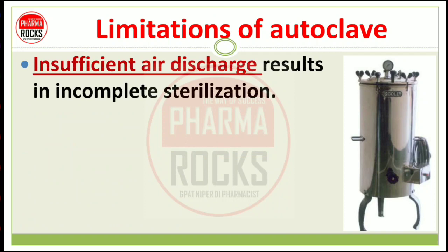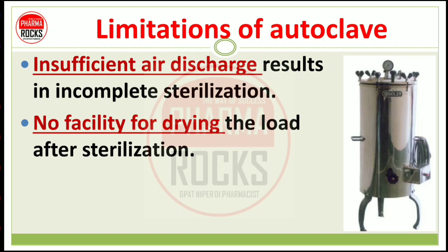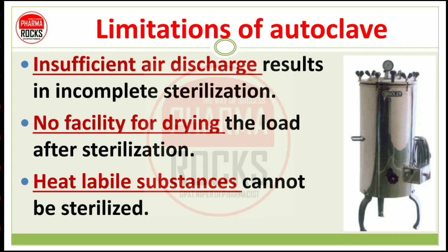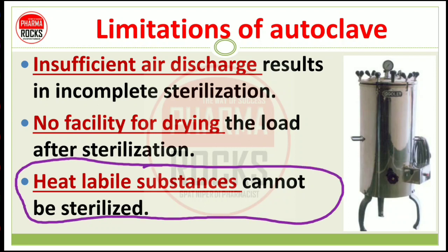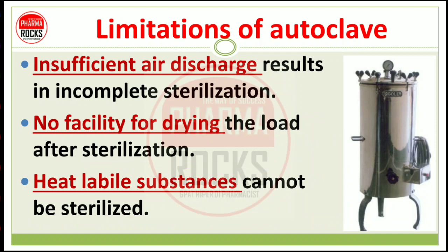What are the limitations of autoclave? Insufficient air discharge results in incomplete sterilization. No facility for drying the load after sterilization — drying ka koi mechanism nahi hai. Heat-labile substances cannot be sterilized — jo thermolabile, heat sensitive material hai usko is technique se sterile nahi kar sakte, because temperature rise hone se article ka decomposition ya degradation hone ke chances hain.